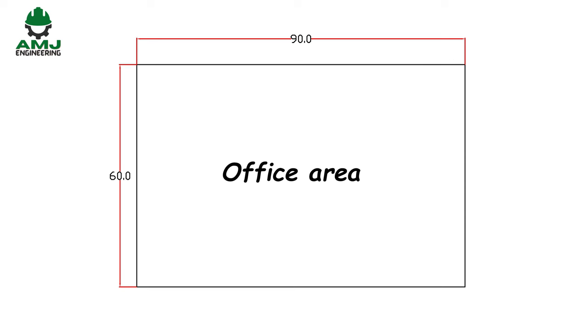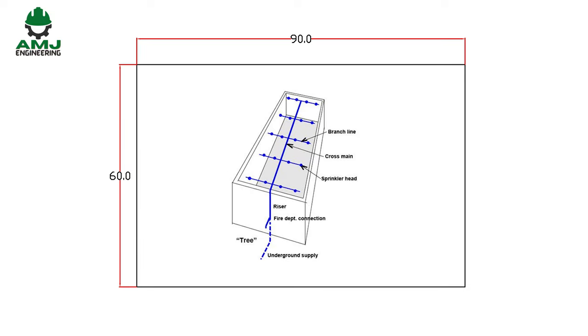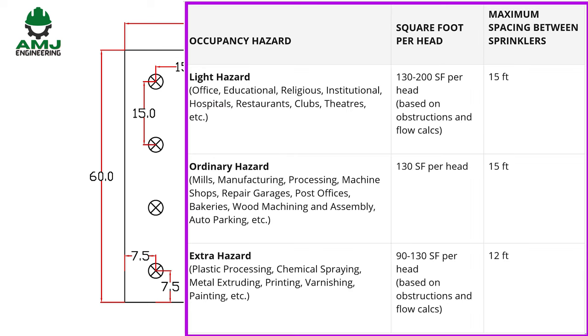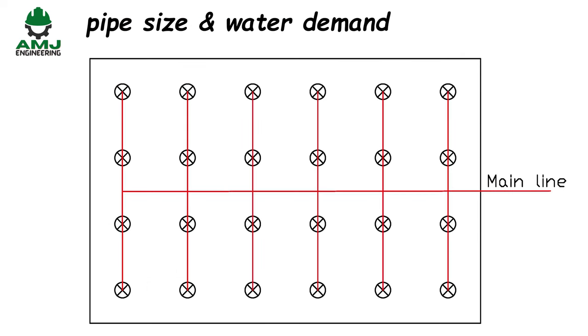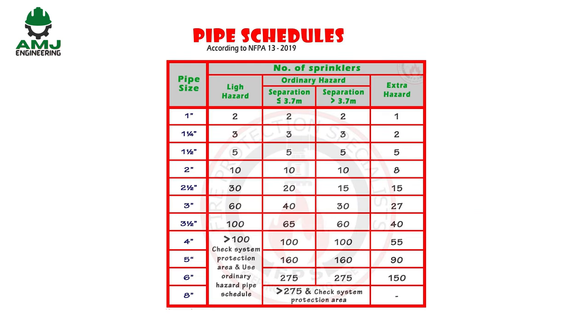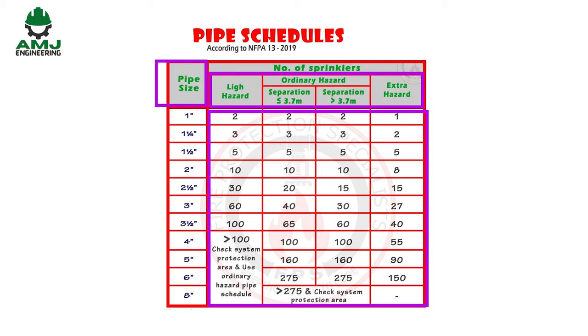Let us take an example: an office area of 90 by 60 feet. Assume we want to design a tree sprinkler system. Being a light hazard, the maximum spacing between sprinklers is 15 feet, and the distance between sprinklers and walls is no more than half the distance between sprinklers. The water demand shall be determined by either the pipe schedule method or the hydraulic calculation method. According to NFPA 13, a pipe schedule system is defined as a sprinkler system in which pipe sizing is selected from a schedule determined by occupancy classification, allowing a given number of sprinklers to be supplied from specific pipe sizes.